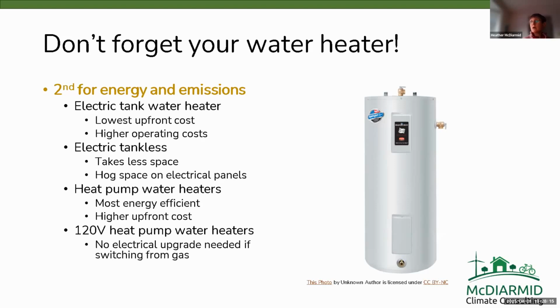One thing to keep in mind with heat pump water heaters is that they take a little longer to heat the water up. So if you've had a shower and run a bunch of laundry and depleted the hot water in the tank, it will take longer to heat back up than with other options. That's why it's recommended you upsize to the next larger tank size when switching from a gas or electric tank water heater to a heat pump water heater, giving you more hot water available and a buffer against running out.